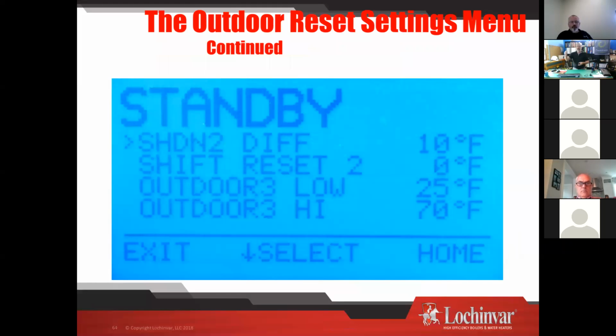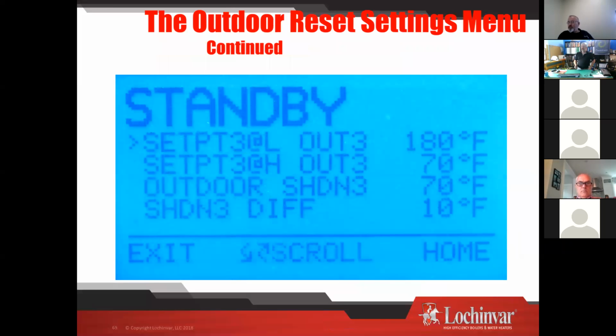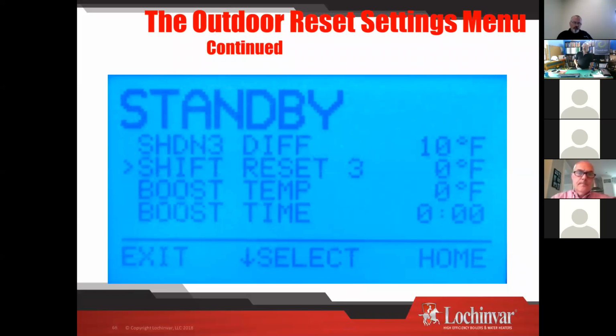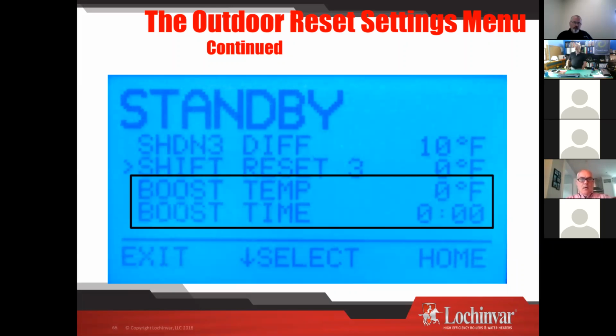All right, and again, you set them up multiple times. 1, 2, and 3. This thing down here at the bottom, boost temp, boost time. This is your other backup. You don't want to put a 2-stage thermostat in. Customer still wants to use night setback, and you want to use outdoor reset because you went out there and said, you put this boiler in, you're going to save gas. And if they rip that outdoor reset off, they're not going to save any gas.